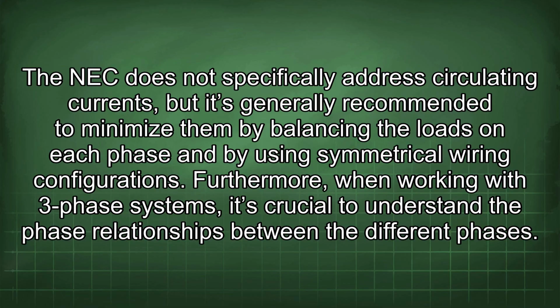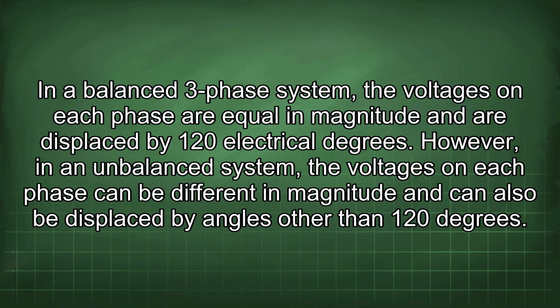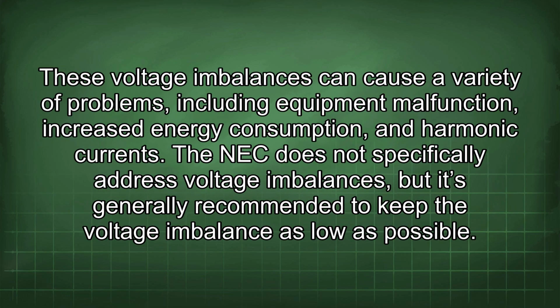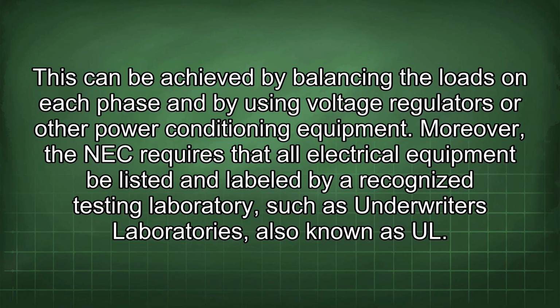Furthermore, when working with 3-phase systems, it's crucial to understand the phase relationships between the different phases. In a balanced 3-phase system, the voltages on each phase are equal in magnitude and are displaced by 120 electrical degrees. However, in an unbalanced system, the voltages on each phase can be different in magnitude and can also be displaced by angles other than 120 degrees. These voltage imbalances can cause a variety of problems, including equipment malfunction, increased energy consumption, and harmonic currents.